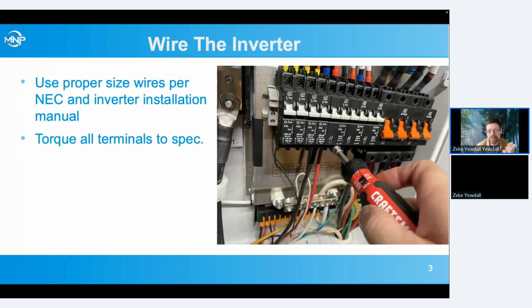First, we want to make sure when we're wiring it, we use the proper wire sizes per NEC and the inverter installation manual, and torque all the terminals to spec. You should have a torque wrench and a torque screwdriver in your toolkit for doing that.